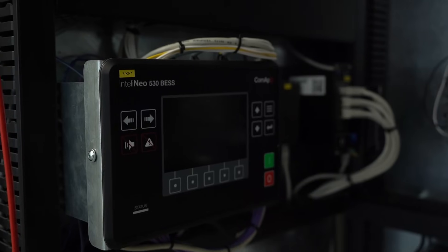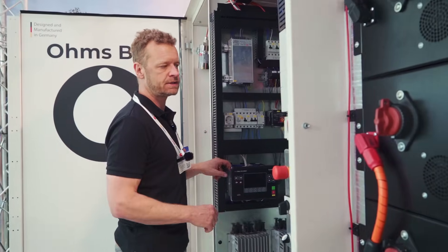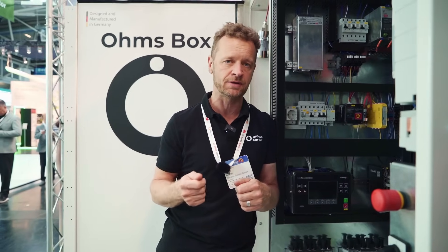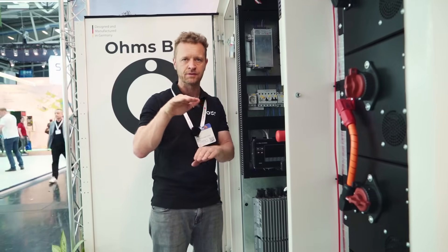The primary mode of this system comes through the Comap controller, which is quite a piece of engineering — a hybrid controller capable of handling megawatts. This system can act as a master controller for a very large mini-grid application. The primary Comap device controls the battery and inverters and two contactors — one for grid in and one for load out. Inside the Comap controller you can set thresholds for voltage, frequency, and power quality to decide whether to accept the incoming grid. If the grid is outside of range, the Comap will disconnect it, because a bad grid will destroy your system. The ATS protects you too, but it's a cruder approach — it simply checks if you're operating within two set limits.